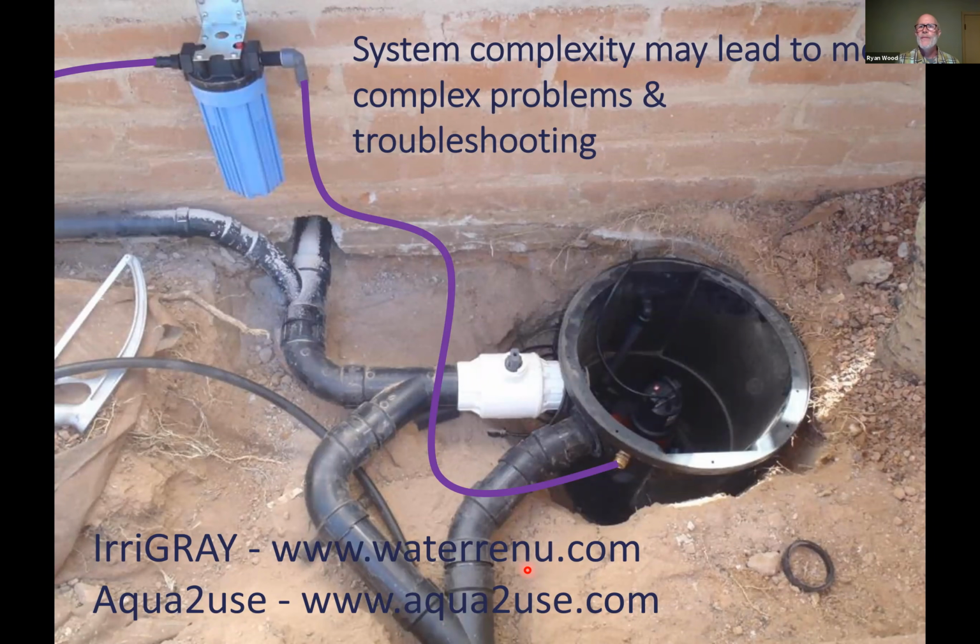It comes through the filters first and then to the pump. So it's going to go through these sheet filters first, and then it gets to the pump. Then the water will kick on the pump and out through the distribution line. With that scenario, you're not going to burn up your pump if you don't clean out the filters. What's going to happen is if you don't clean the filters, then it's going to overflow to the sewer, and it's not going to make it to the pump. So the scenario there is you're not burning up your pump, but you're losing your gray water.